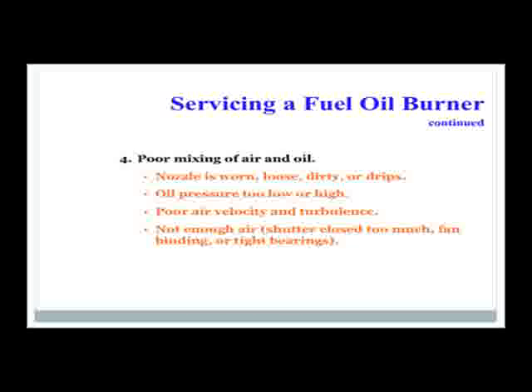If there's poor mixing of oil, check whether the nozzle is worn. Check oil pressure too low or too high. Check for air turbulence and velocity. You might not have enough air. Puffbacks are caused by water in oil or delayed ignition. Go back and check all your ignition parts and oil pressures and transformers again.